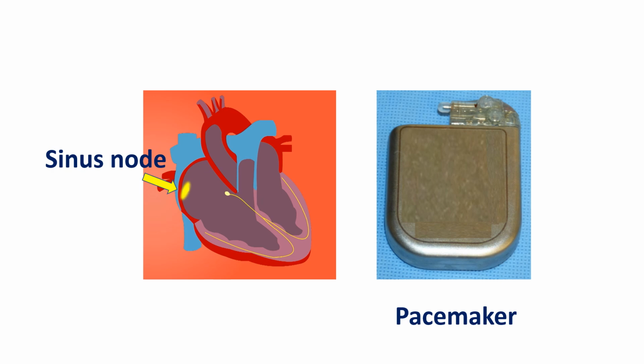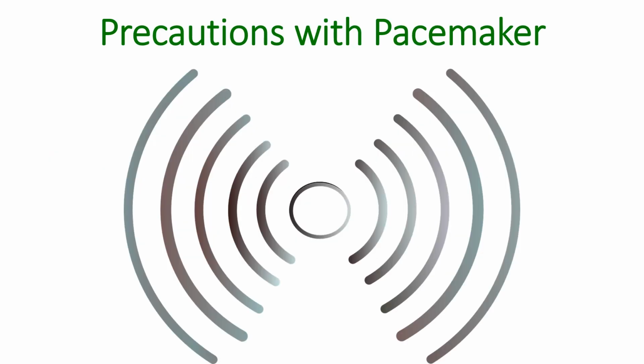pacing. Dual chamber pacemakers are AV sequential pacemakers which pace the atrium first and then the ventricle after a short programmable AV delay. Single chamber pacemaker can pace either the atrium or the ventricle, usually the right atrium or right ventricle. Being an electronic device which functions on an inbuilt battery, pacemaker function can be interfered with by strong electrical and magnetic signals in the vicinity. This is known as electromagnetic interference of pacemakers.